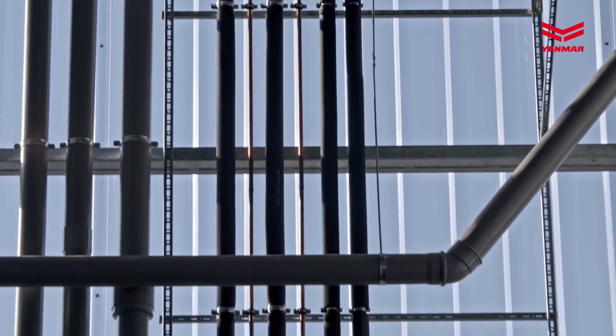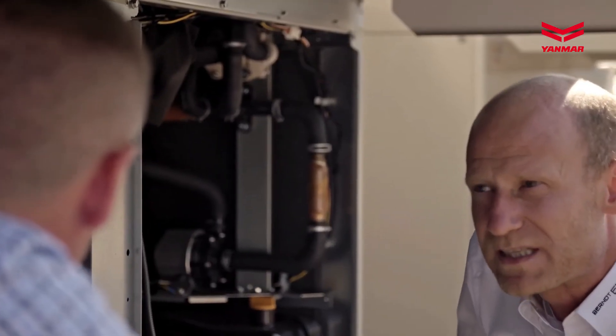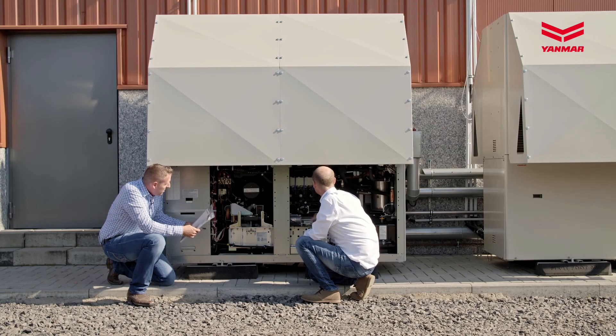The arguments that have already been mentioned caused us to think differently. My name is Markus Becker. I'm responsible as sales engineer for planning, installing and developing the gas-driven refrigeration unit. We use gas heat pumps for air conditioning of buildings, and now we can transfer this reliable and efficient technology into the refrigeration sector. We have a double effect that makes these units twice as efficient — cooling down the cooling spaces, while engine waste heat is used to defrost the evaporators as well as for heating domestic hot water, used for heating sanitary facilities and drinking water for free.